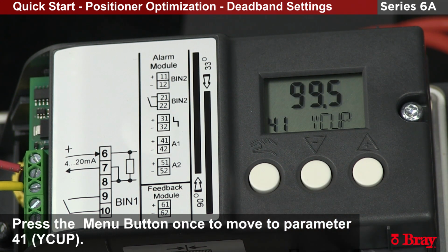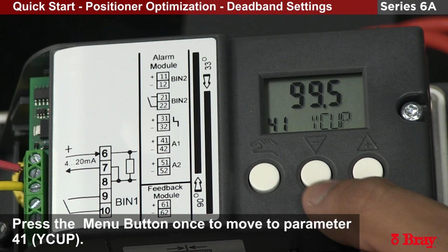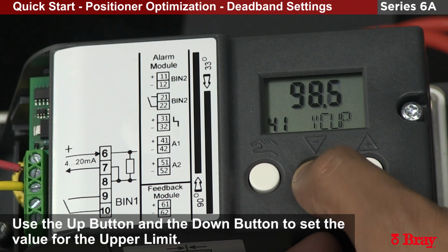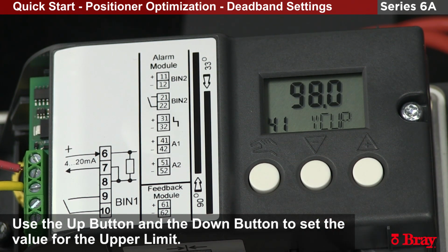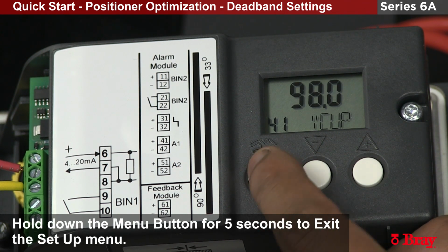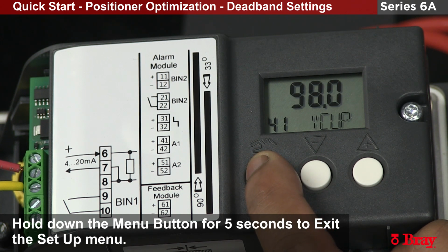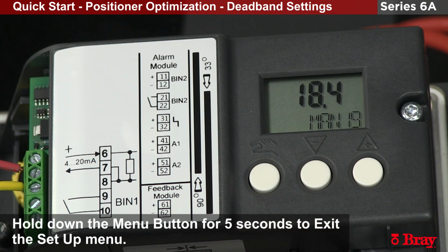Hit the hand button again. We'll do the same thing for the full open position. Right now it's set to 99.5. We'll reduce that to 98. Hold down the hand button to get out of the setup window. And then hand button once to pull out of manual mode and into auto.